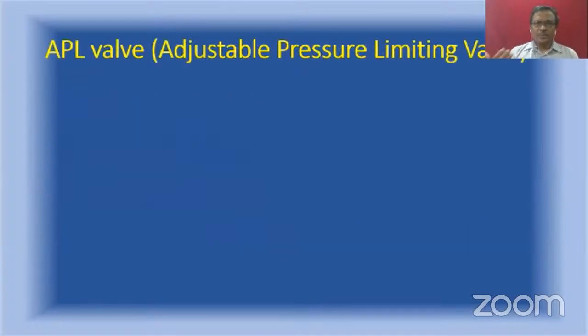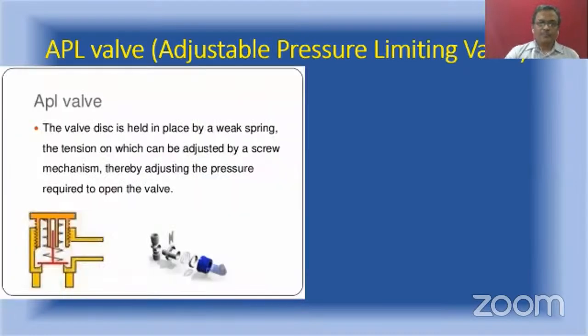Let me tell you something about the APL valve. See, the APL valve has a disc which is held in place by a very weak spring. No, it is not a strong spring. The tension of the spring can be adjusted by a screw mechanism. Look at this picture. You can see the disc here. When the valve is in fully open position, the tension on the spring is very minimal. So this open position is used whenever the patient is spontaneously breathing.